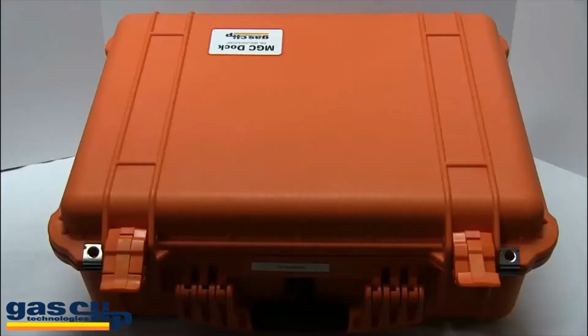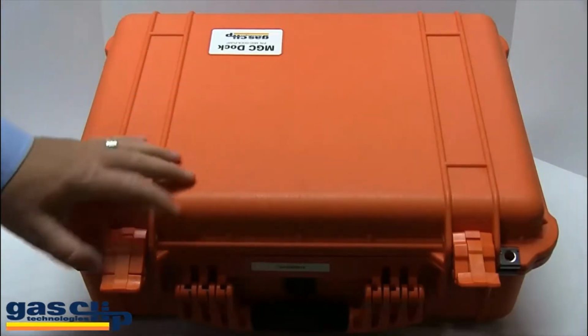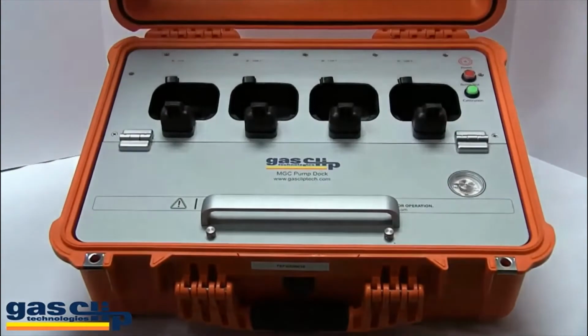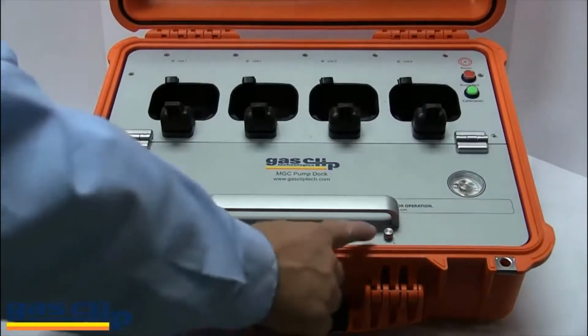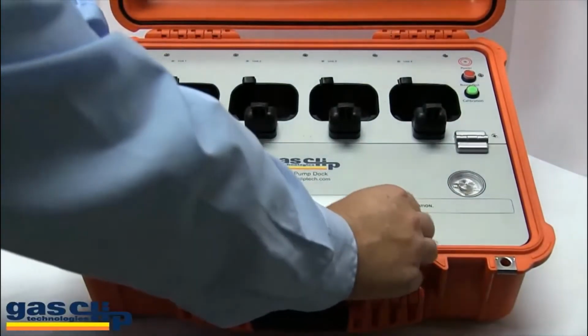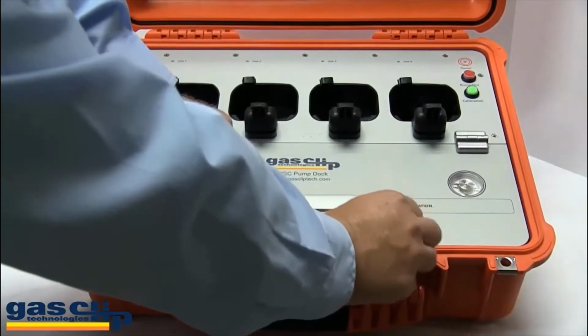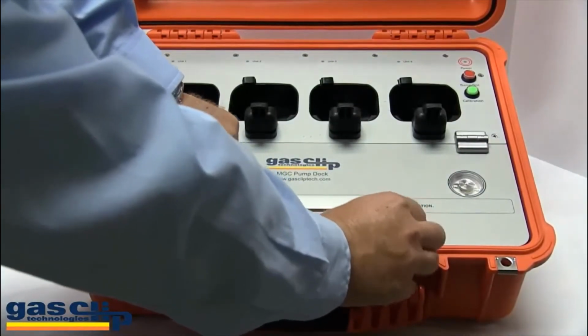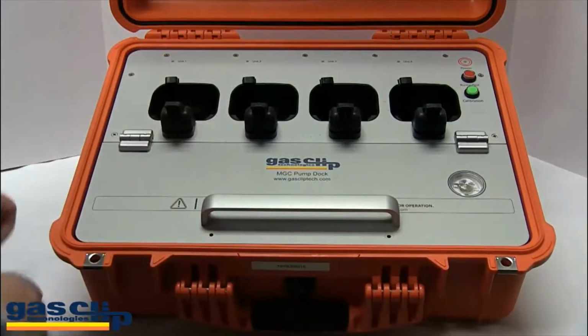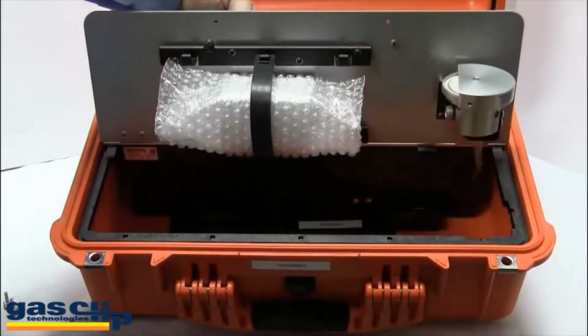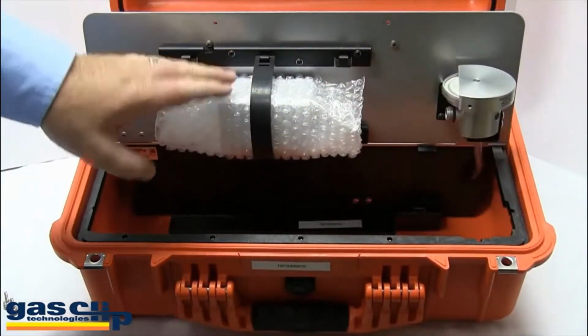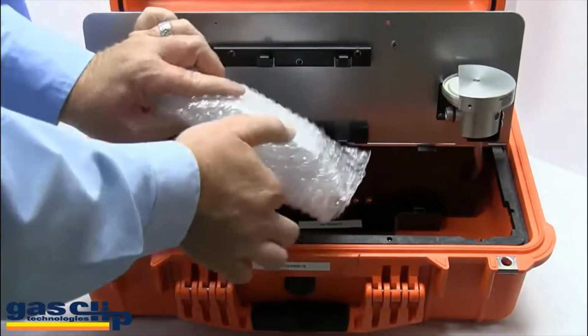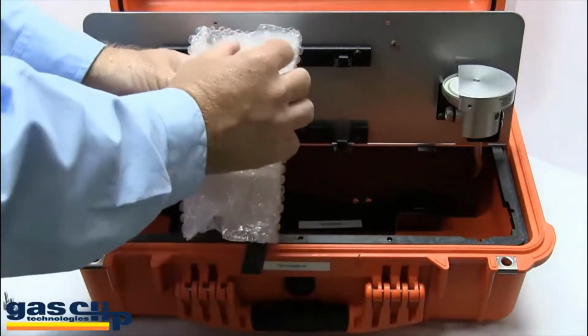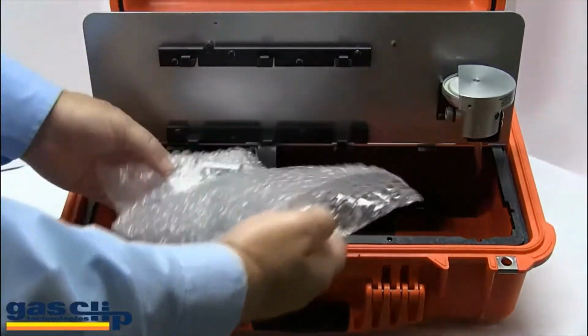To bump test and calibrate your Mgc pump monitors, we also have an Mgc Dock Station. Once you open the dock lid, you will see two thumb screws here at the bottom. Remove those and set them to the side. Upon opening the lower door, you will notice that you have a bubble wrap bag. Go ahead and remove this and you can open it up.